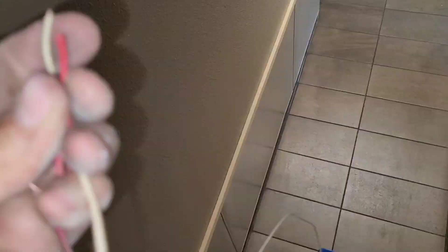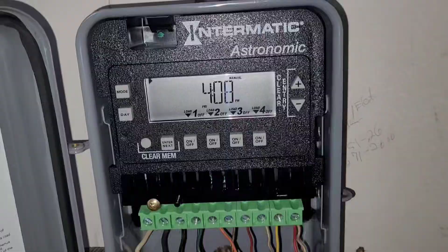So these wires have power to them and are hooked up to nothing, and need to be disconnected at the other end. So yeah, I think I do need to take out the jumpers, and I need to just get these pairs hooked up onto the dry contacts. One of them, I don't know what it's for, but I'm guessing that's the kitchen AC, because they put that jumper in there feeding power to all of them. So that's what's wrong — they hooked the wires up all incorrectly in addition to putting those jumpers in.